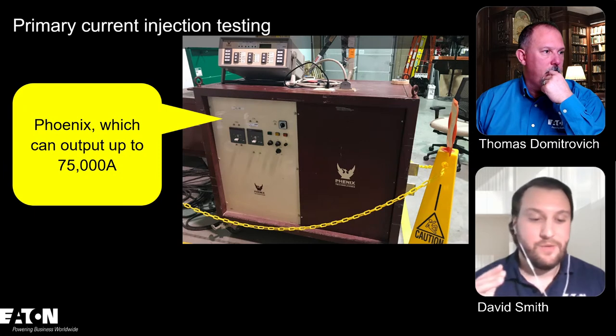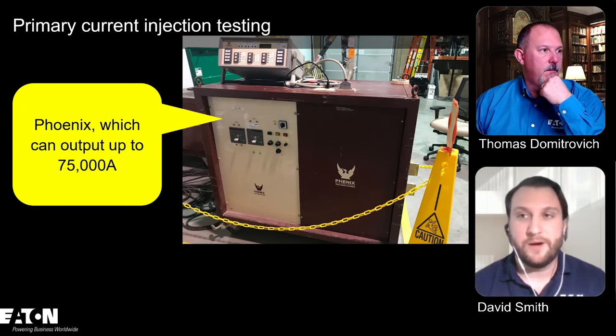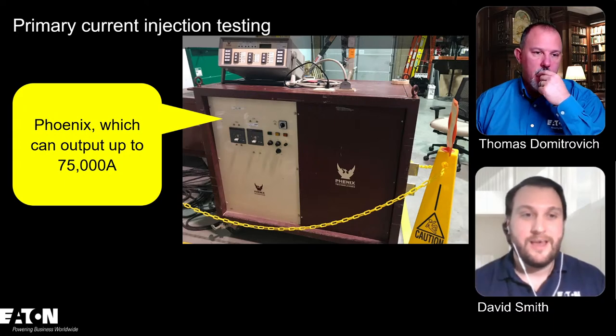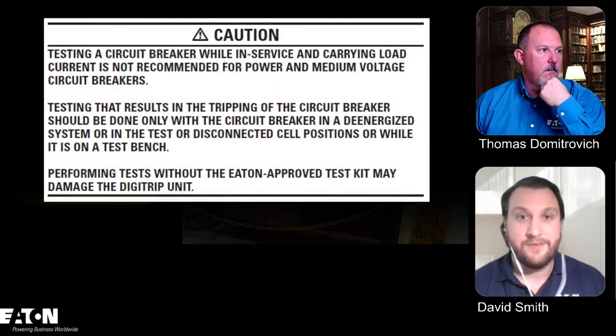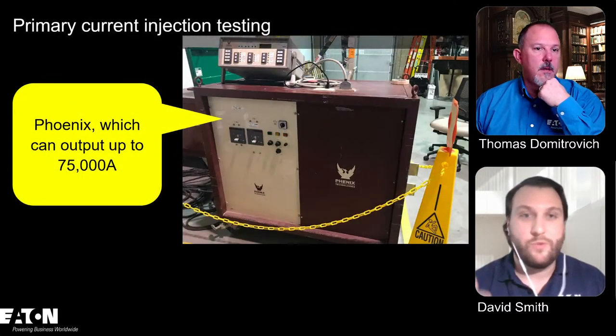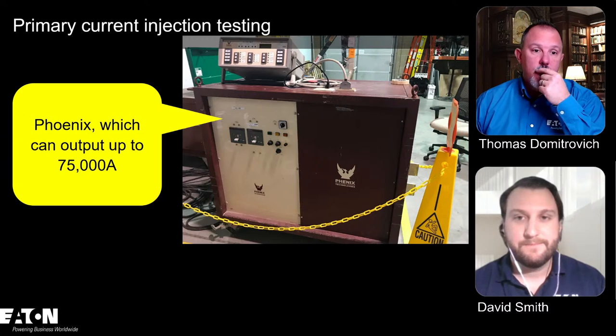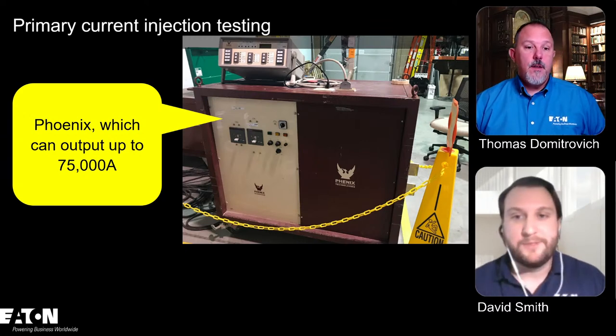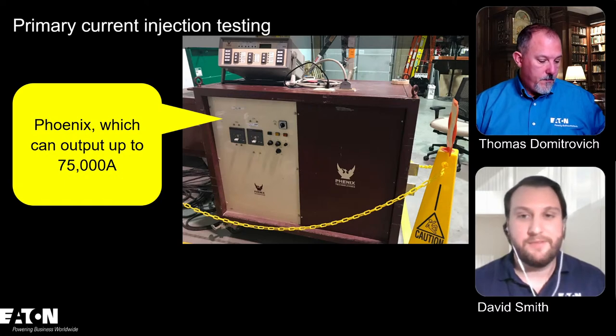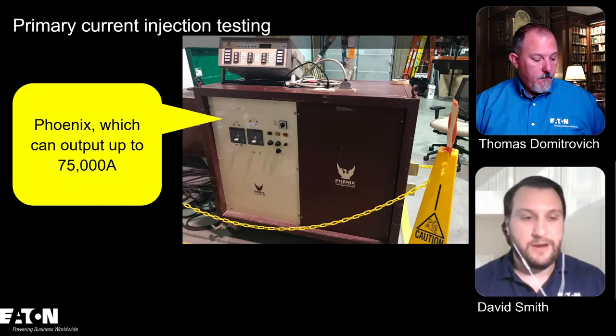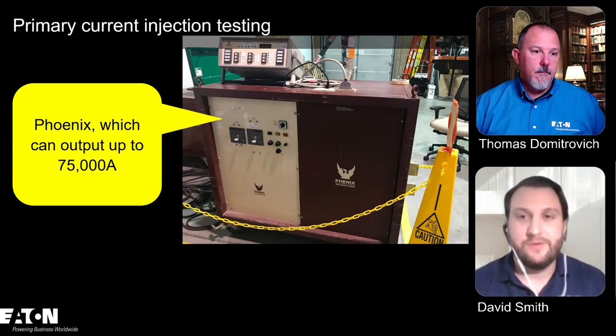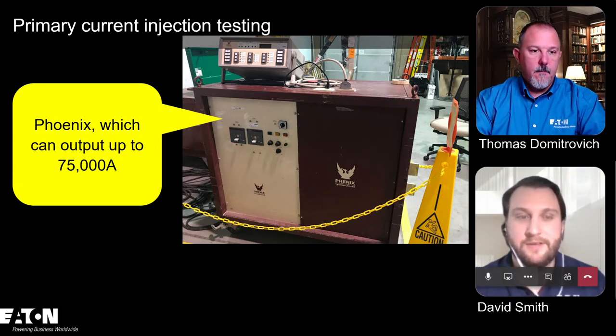Now, I'm not saying primary or secondary whenever it comes to circuit breakers is better or worse. What I'm saying is that you can do these kinds of things and you have the options to do it. And plus, Tom, you were talking about this earlier: if you're going to do your secondary or primary current injection testing for 240.87, and you're already in the field doing this kind of stuff, you might as well do your GFPE testing while you're already there. That's right. It absolutely makes sense to document this with the checklist we've given you. That'll cover everything that you need there. Check out the white paper we have on 240.67 or 87 whenever it comes to this stuff.